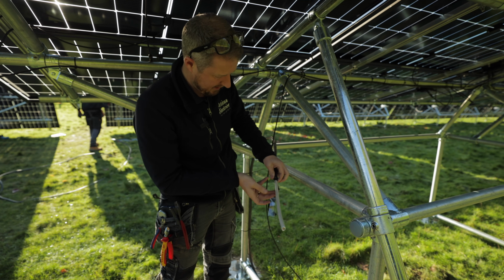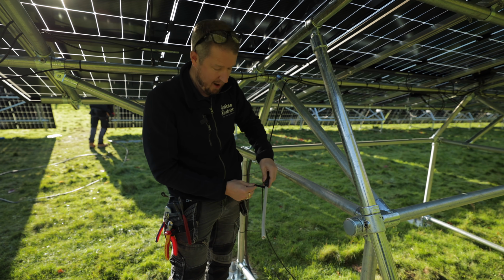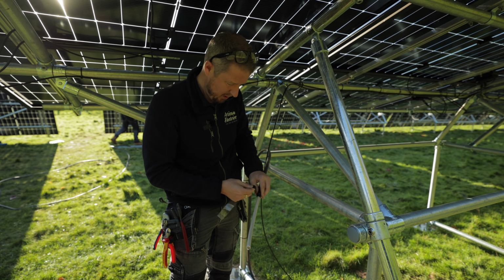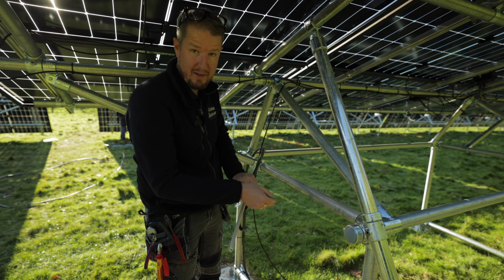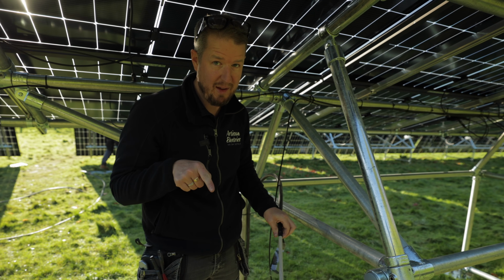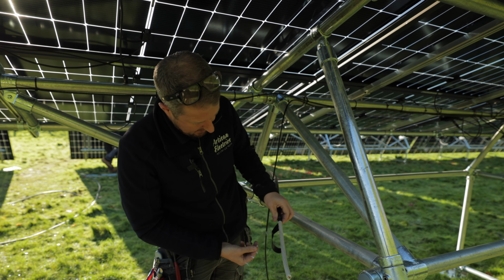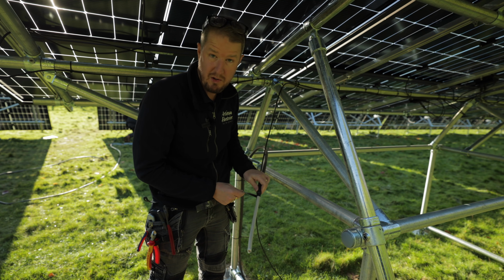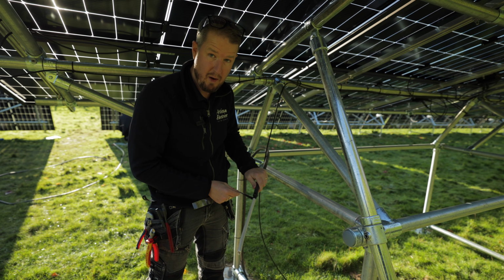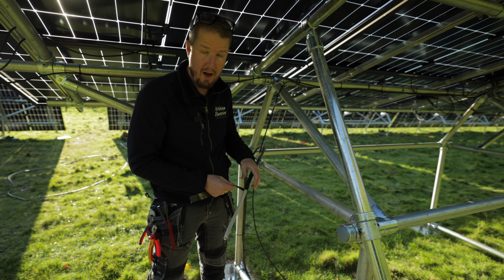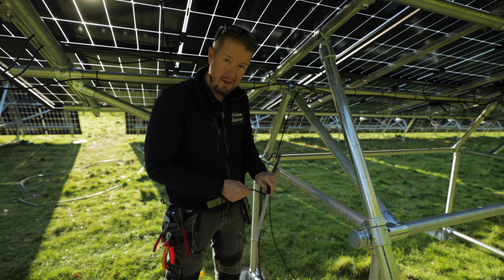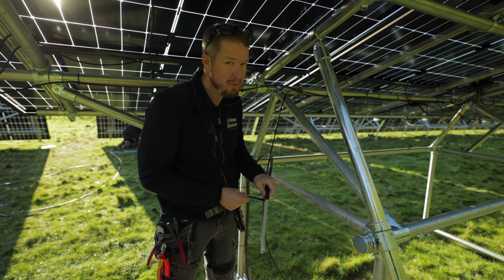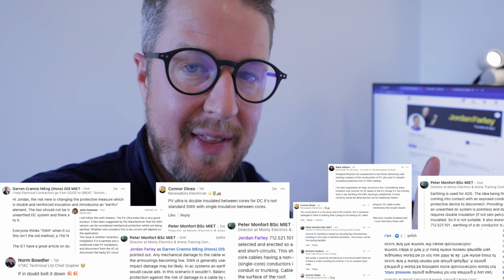Actually, this is a really interesting question for debate: should I be earthing the armouring of this cable or not? To be honest, I thought that we should - let me know what you think in the comments before I tell you the answer, I'll tell you in a few minutes. It seems logical, right, because it's a steel wire armoured cable, we're used to having to earth it, especially if it's buried in the ground. But because it's DC, should you be earthing it? I've just caused quite a stir on LinkedIn by posing that question of whether the armouring of a DC cable should be earthed or not.